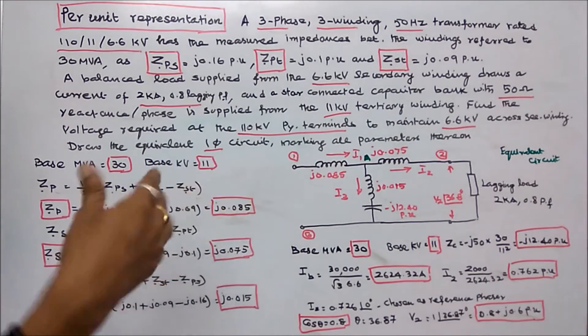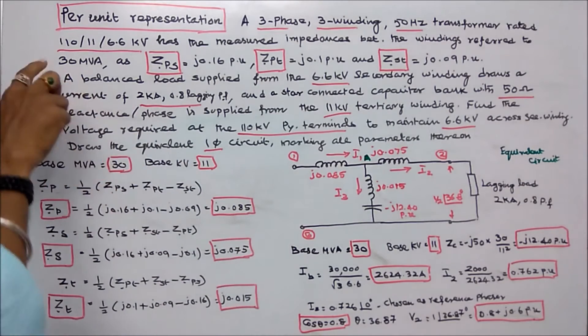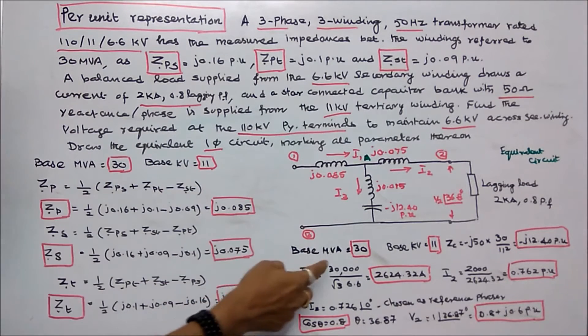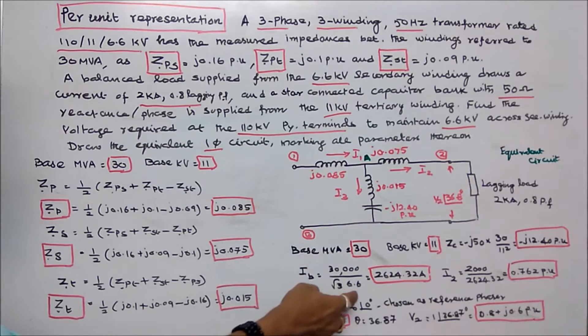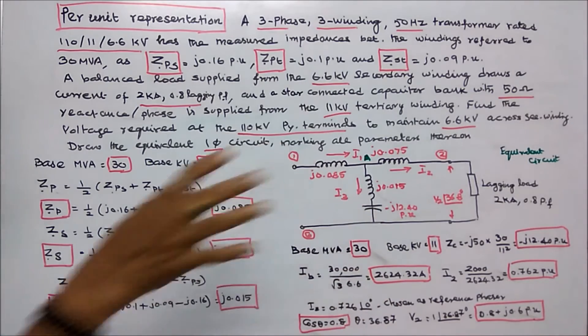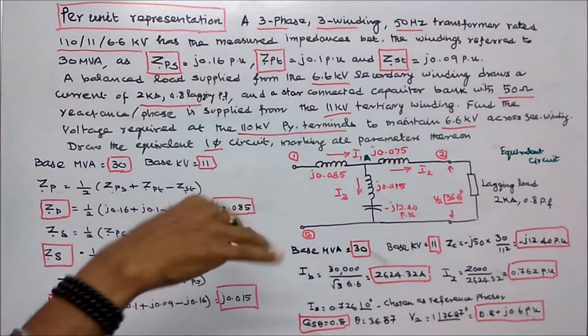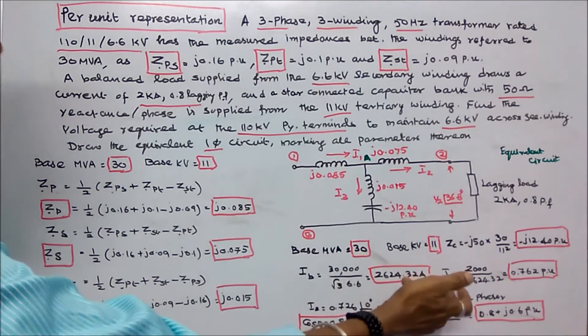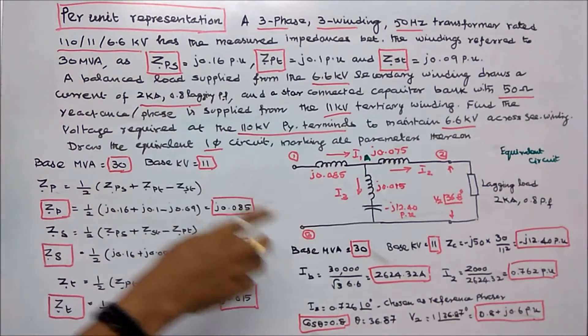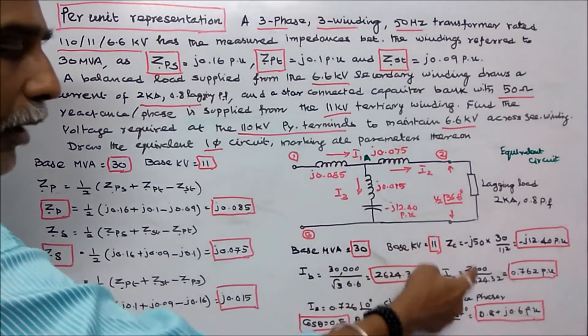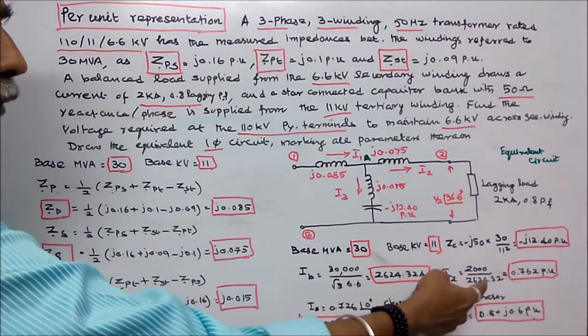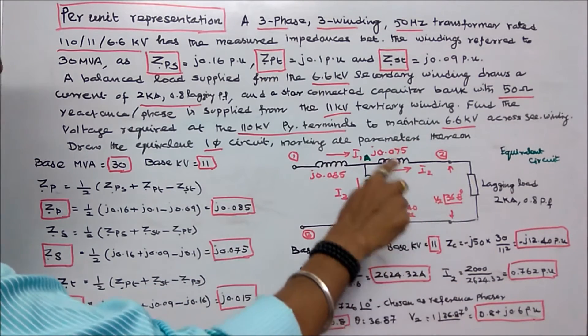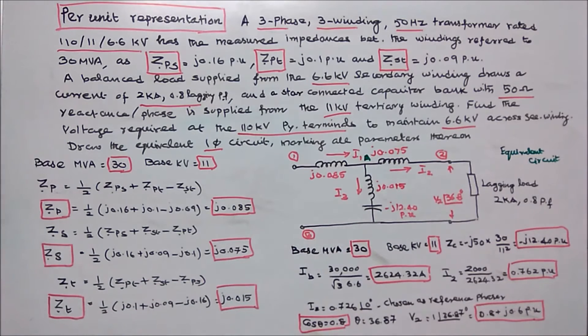Next I have to find the base current. Here 30 MVA, that is 30,000 divided by root 3 into 6.6. Base current is 2624.32 Amps. Once I know the base current I can easily find the secondary current I2. I2 is equal to 2 kilo Amps, 2000 divided by 2624.32. I2 is equal to 0.762 angle 0, that is chosen as a reference.